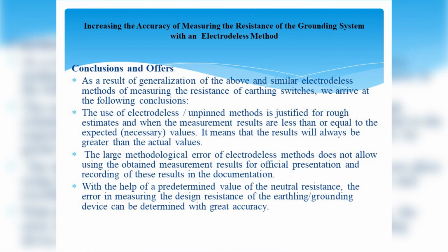As a result of generalization of the above and similar electrodeless methods of measuring the resistance of earthing switches, we arrive at the following conclusions. The use of electrodeless unpinned methods is justified for rough estimates and when the measurement results are less than or equal to expected necessary values. It means that the results will always be greater than the actual values.